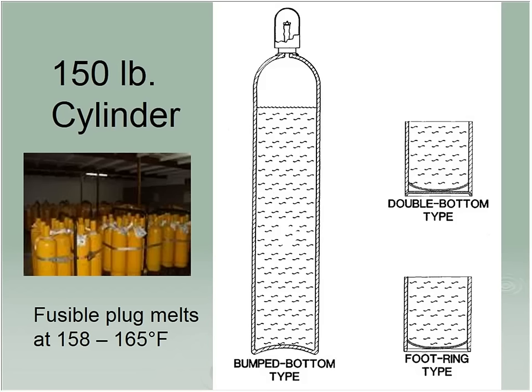containers. If you've got a very small operation, you might buy it in 150-pound cylinders. They look like your standard gas bottle. It's used in an upright position. It has a single valve at the top. That valve has a fusible plug in it that will melt at roughly 160 degrees Fahrenheit, give or take. The idea being that we don't want this thing to explode. If it's in a fire, it'll just release the gas and let the firemen deal with it, I guess.